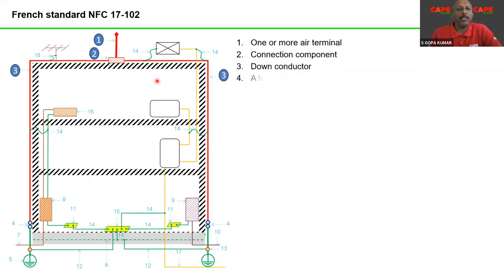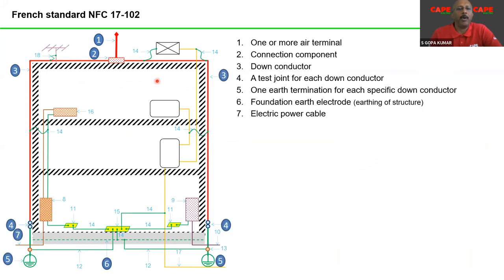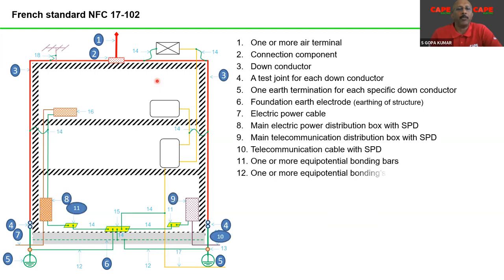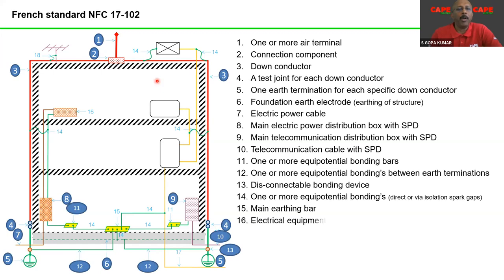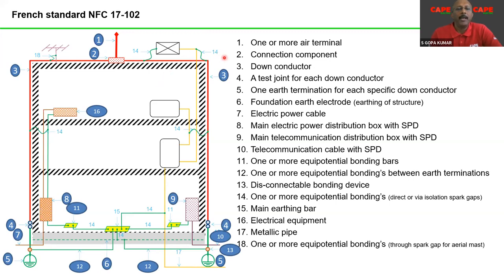If we look at the French standard, it does not explain ESE as one rod, one down conductor, and one earthing. It explains a properly equipotentially bonded, proper lightning protection system consisting of several components. So basically, the French standard is similar, I would say, over and above IEC 62305, you are making some more arrangement. If you read the NFC standard, it explains lightning protection as: you make a Pakka lightning protection system as per 62305, and over and above you make some additional arrangement like an ESE air terminal. That means the story, which is the propaganda made in India, one rod, one down conductor, one earth electrode, is absolutely wrong.